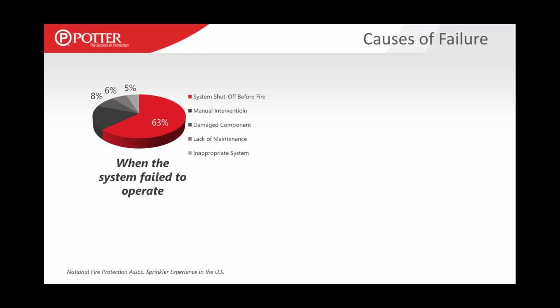The slide's a little hard to see sometimes, but about 2/3 of the time when the system fails to operate, it's because the valve was shut, right? And the rest of the times we generally know the categories of failures: manual intervention, somebody did something to defeat the system, damaged components, lack of maintenance, things like that. The question you ask yourself: are these preventable? Are they things that we can identify during an inspection or test and correct? And the answer is almost always yes, right? If we can identify a shut valve, of course we can. Is that a big burden on the owner to do? And the answer is no. It doesn't cost a lot of money to have a valve looked at every so often to make sure it's still open. So those are some of the decisions that go into what rules end up in NFPA 25.